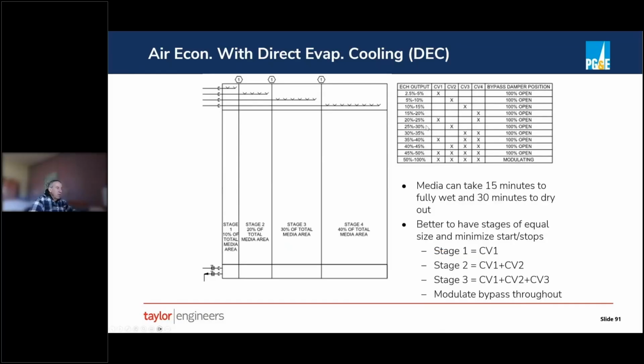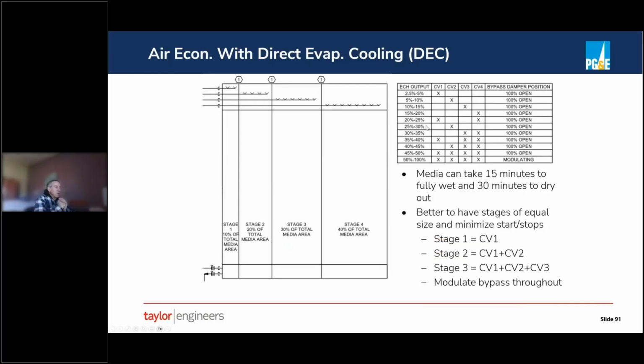We found that didn't work very well. And the reason is that the media can take 15 minutes to get wet and even longer to dry out. And if you turn off this stage and turn on this stage, you're really going to have both of them operating for quite a long period of time. And so you're sort of fooling yourself into thinking you can get that fine of a control, because it takes a long time to turn on and turn off. Kind of like steering a super tanker, oil tanker. Turn the wheel, but it might take a long time before it actually starts turning.